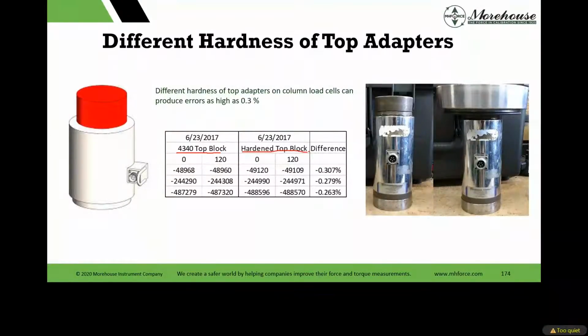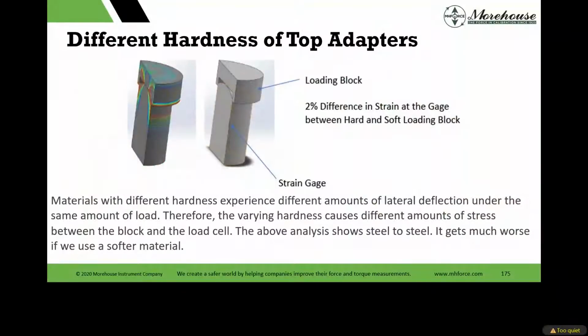So looking at these differences, I did this the same day, I did different days, I did over the weekend, and at the end of all this, I could say, undoubtedly, with this setup where the customer did not send their blocks, we used something softer not to indent the load cell, versus using a hardened adapter. The difference on this specific load cell was about 0.26 to 0.307%, just from swapping top blocks. It happens all of the time. People send us stuff without their adapters. I'm sure they're sending you stuff without adapters, and you're giving them results, and the results are only valid if they're using the same hardness of material that your adapters are, if they haven't sent theirs.